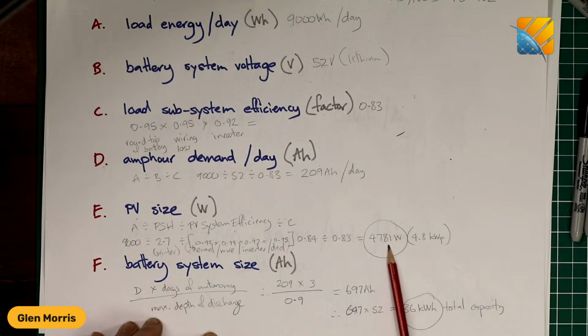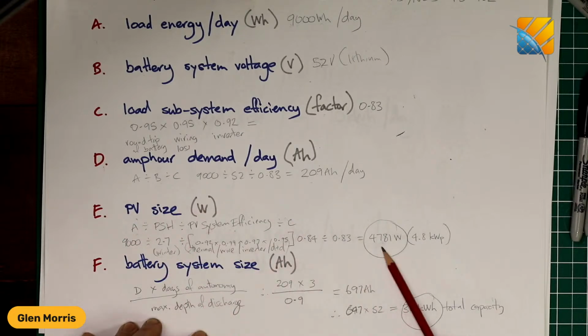And that's sizing my PV for this design with peak sun hours in winter of 2.7, which is basically here in Melbourne, north facing at about a 50 degree tilt. I need 4.7 kilowatts of panels. It's not too bad, actually, 4.7 kilowatts of panels. But that would be unshaded, north facing at a 50-degree tilt. So you can see this number can easily be increased to allow a little bit of overcapacity for those poor days, and it's often the cheapest way of reducing the cost of your battery storage, because I'll get onto that last.